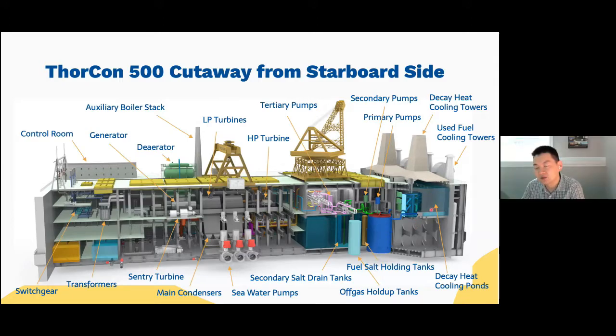Here is the decay heat cooling pond, and we have this decay heat cooling tower. The decay heat will be transferred by water to this part, which we'll show in more detail. Just remember, here is the location of the decay heat cooling pool, which has a lot of water, and this water can last almost half a year to cool the used fuel without any external power. Underneath the cooling pool, there's a space that's always left empty — a ballast space. If there's additional steam from the cooling pool or some other place in the nuclear island, the steam can go to this space, so you can relieve pressure from other parts of the plant without releasing it to the atmosphere.